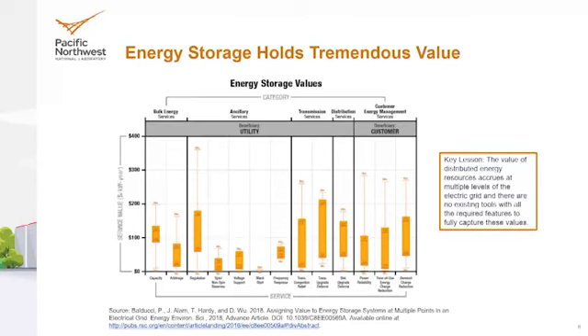While you may hear from vendors that you can get 90 to 92% round-trip efficiency, when engaged in economic operation and including all power conversion systems, standby losses, and auxiliary loads, that number begins to dive—getting into the low 80s and even high 70s—and it differs from one application to the next. So it's important to understand how these different characteristics apply to different services or value.